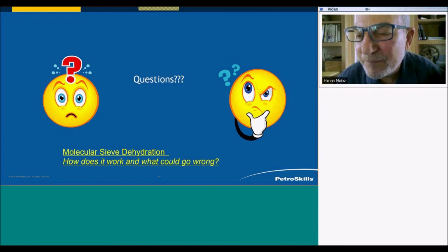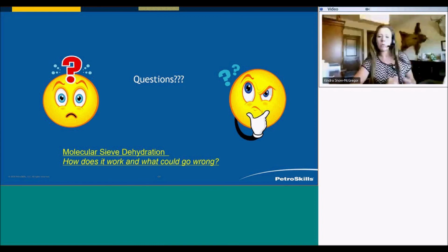Okay, thank you. All right, how about another question? When you're running your breakthrough tests, is it possible to run with the chilled mirror method, the Bureau of Mines method? Or what analyzer do you recommend? They're asking because the response times of Panametrics and Ametek products are different, for example. Yeah. When you're looking at, go ahead.